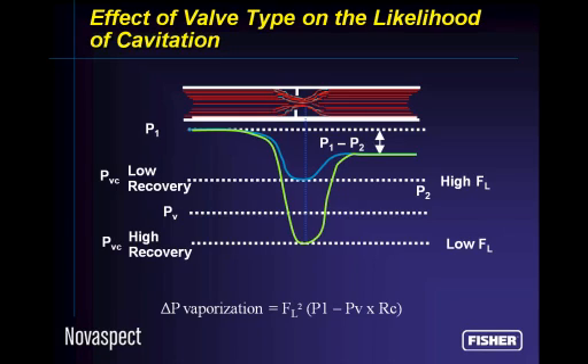You can see that PV, that vapor pressure line there, obviously the valve that's the high recovery valve is going to drop below that line in this particular instance, whereas if I applied a globe valve, a low recovery valve instead, I might actually avoid this issue. So by picking the right control valve, we might actually avoid this cavitation issue.